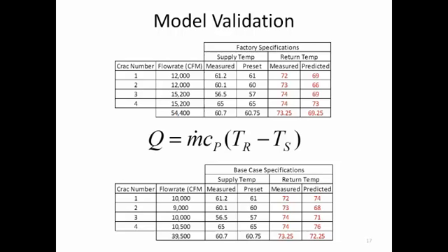Yeah, and it's also a little bit complicated because the CRACs emit air, it comes up into the room, goes through the racks, and the air that goes back to any one of the CRACs is not necessarily the same air that left it. So you've got the supply air mixing with what's coming from other CRACs, and then returning to any given CRAC. So it's not a one-to-one correspondence of the air going out and that being the same air coming back in.